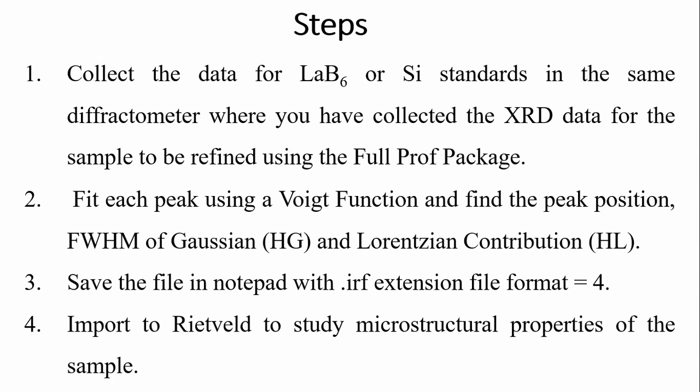So the first step we are going to follow is to collect the data of LaB6 or silicon standard in the same diffractometer where we have collected the XRD data for the sample to be refined using the FullProf package.